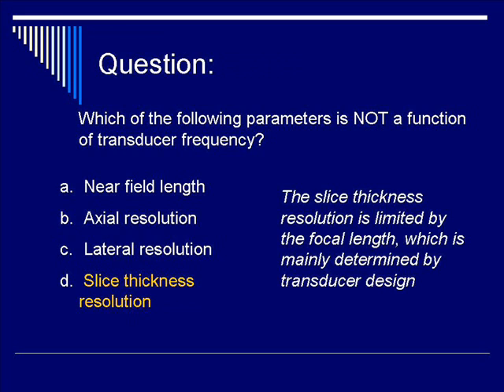Recall that near-field length, axial resolution, and lateral resolution are all dependent on frequency, but slice-thickness resolution is limited strictly by transducer design, namely the focal length. If you operate outside the focal zone, you're susceptible to slice-thickness variability.